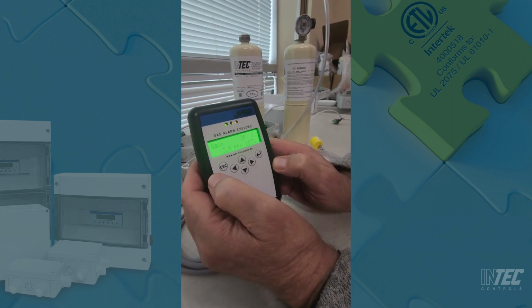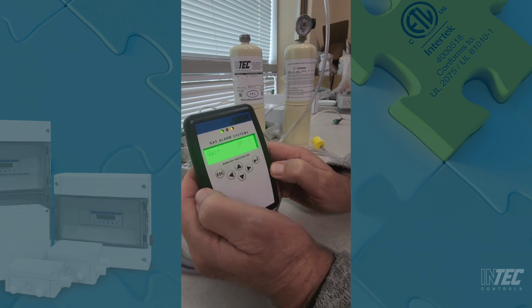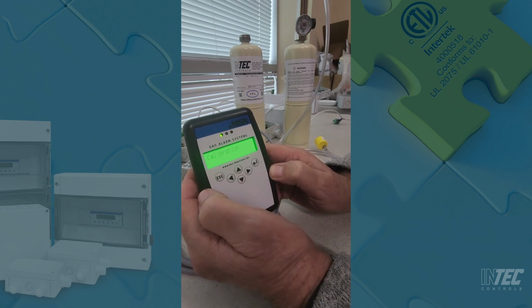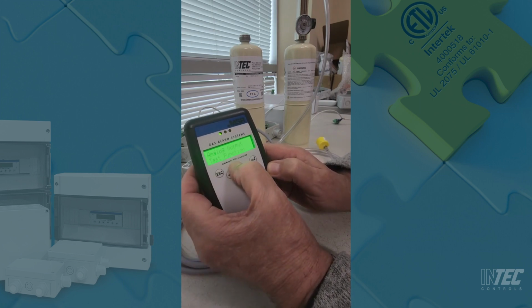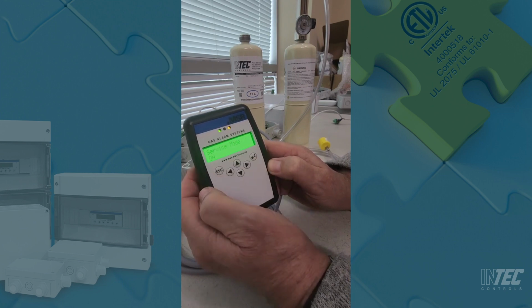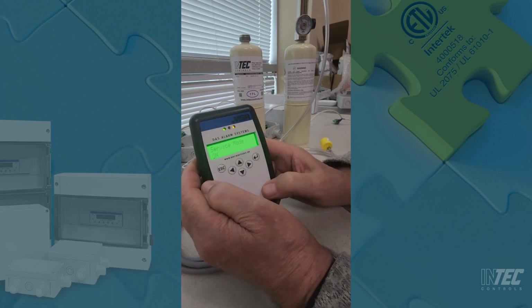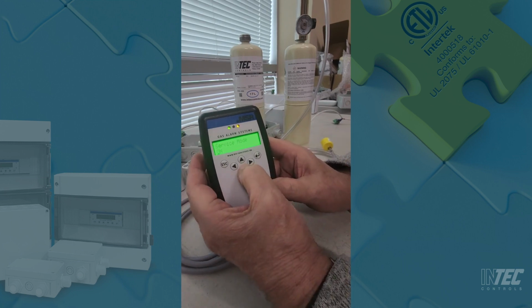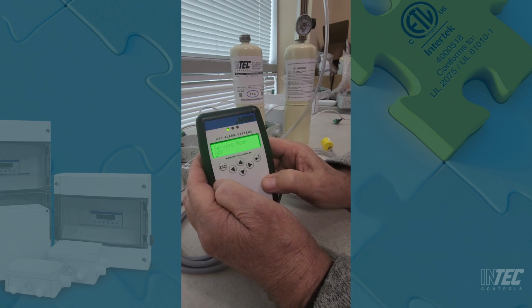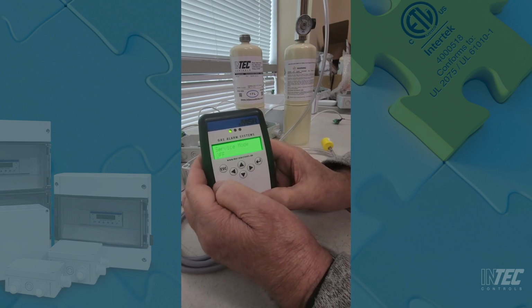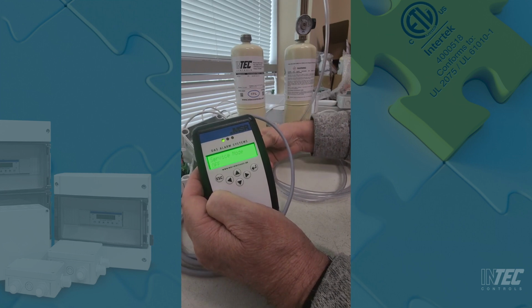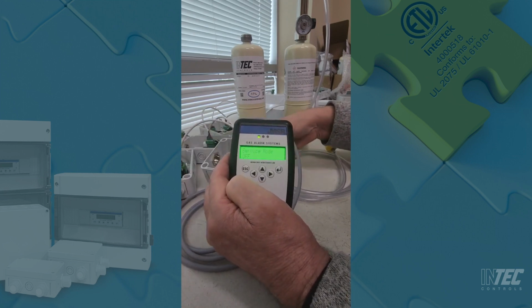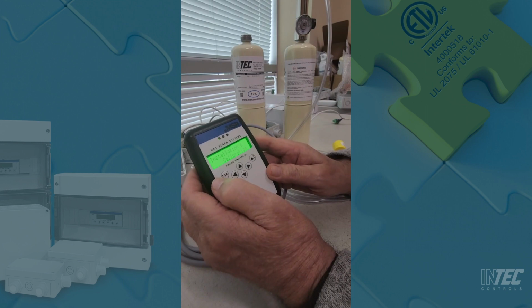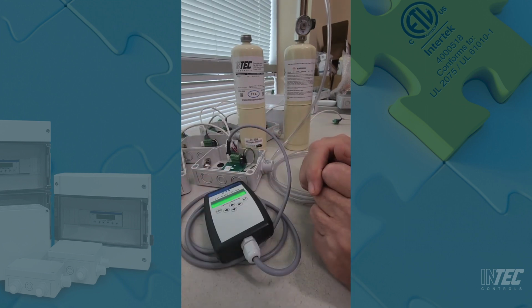At this point, you just hit the escape button. Escape button again. Escape button again to go back to calibration. Now we're going to just arrow up to service mode on. I'm going to hit the enter button. That little cursor will pop up. Down or up arrow to change it to off. Hit enter. And now service mode is off. You notice that the yellow LED on the sensor is no longer blinking, and you have now calibrated the sensor.